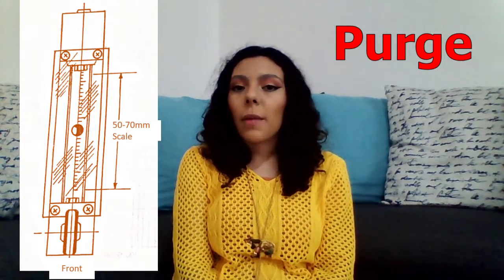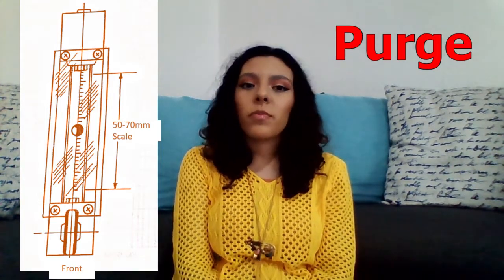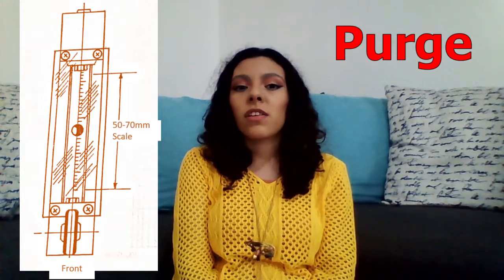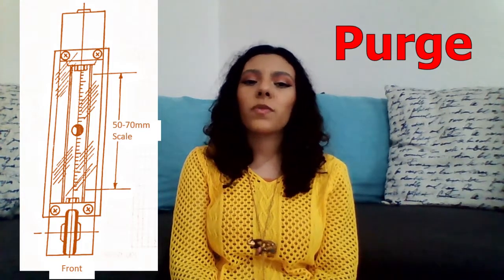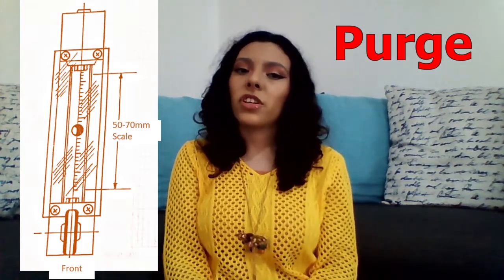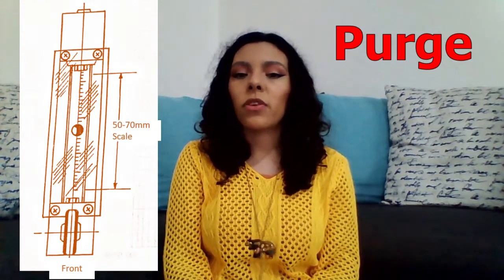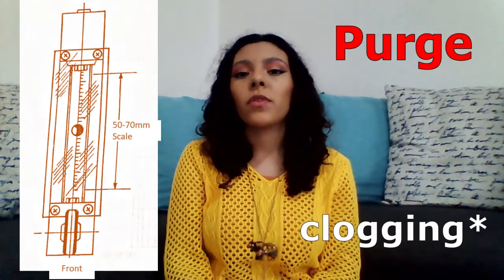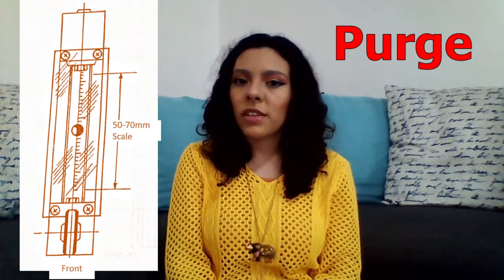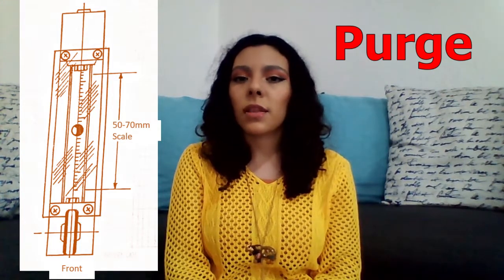Some of its typical applications are the hydraulic purging of the mechanical seals of the general pumps of the plant, the measurement of the level by bubbling, the purging of differential pressure elements for the flow measurement, avoiding the clogging of the pipes, and the purging of the instruments that work in corrosive or dusty atmospheres.